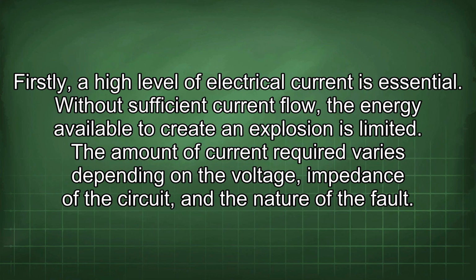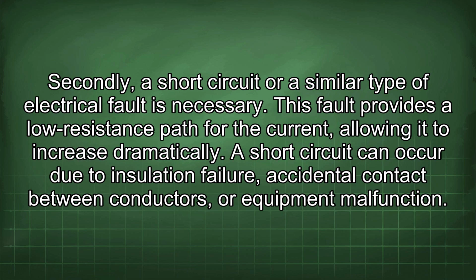Firstly, a high level of electrical current is essential. Without sufficient current flow, the energy available to create an explosion is limited. The amount of current required varies depending on the voltage, impedance of the circuit, and the nature of the fault. Secondly, a short circuit or a similar type of electrical fault is necessary. This fault provides a low resistance path for the current, allowing it to increase dramatically. A short circuit can occur due to insulation failure, accidental contact between conductors, or equipment malfunction.